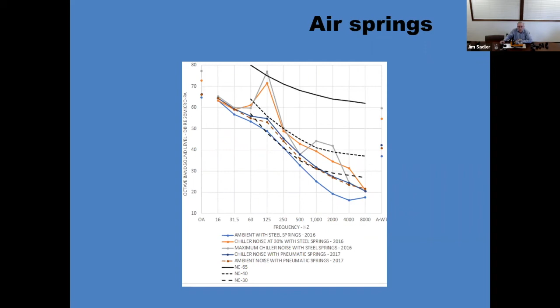This is just some of the same information with the NC curves. So we went from an NC 65 down to an NC 30 with the introduction of the air springs. And keep in mind that, again, that chiller was isolated. It was isolated on steel springs. We didn't realize this improvement until those were replaced with air springs. Another aspect of air springs is that if you have a large enough diameter and enough air springs, you can support anything.